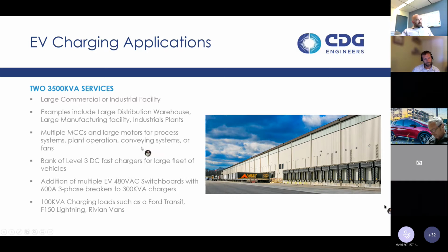The idea being large, multiple MCCs, large motors for plant operations, conveying systems, fans, that kind of thing. The intent would be to put in level 3 DC fast chargers for a larger set of fleet vehicles, rather than a dozen vans, maybe multiple dozens of vans. Similar type of power arrangement, just scaled up, looking at the same kind of charging load, 100 kVA.